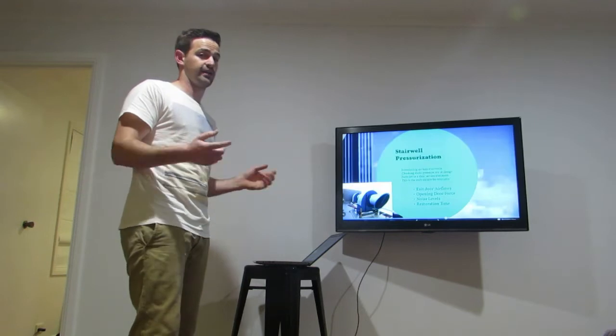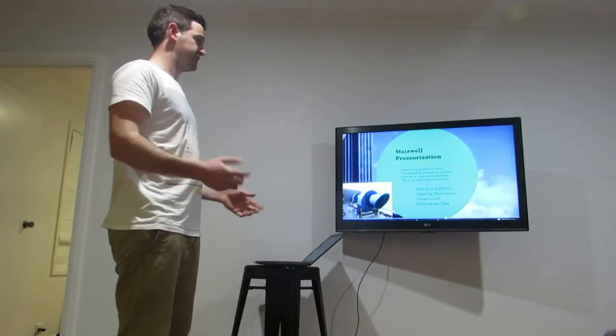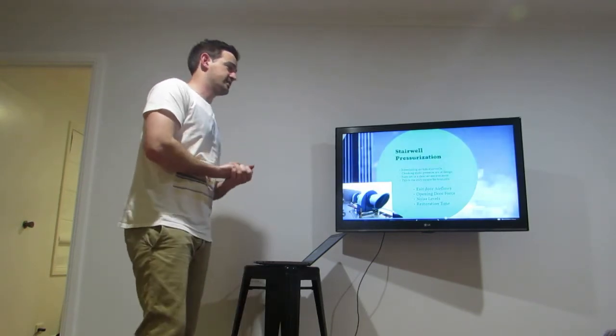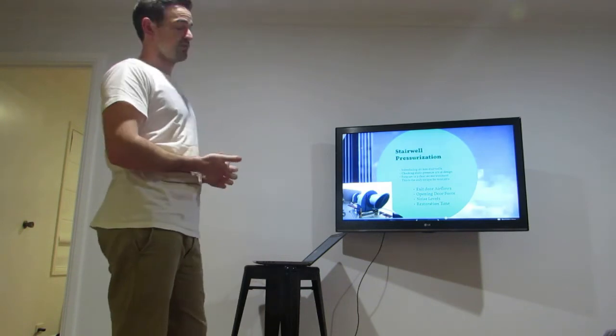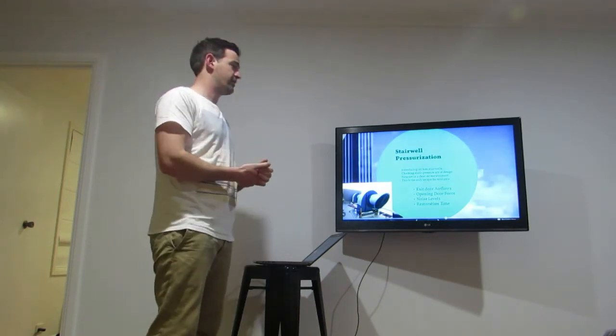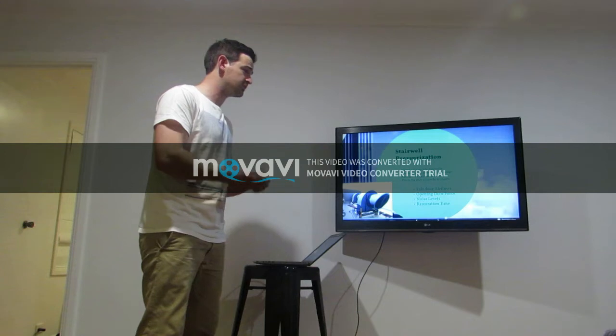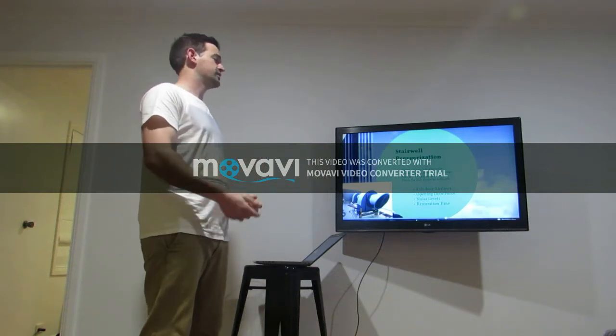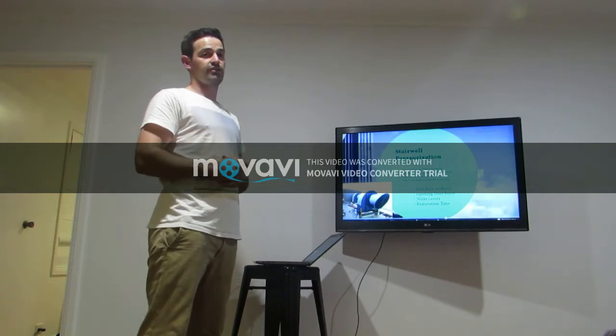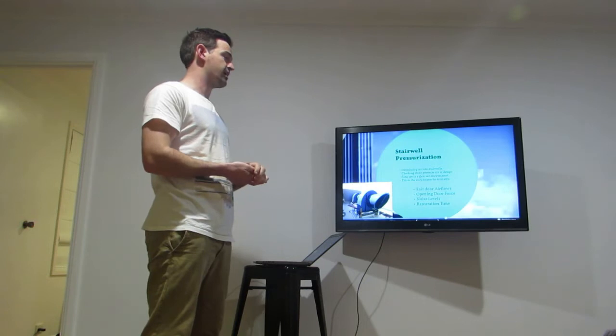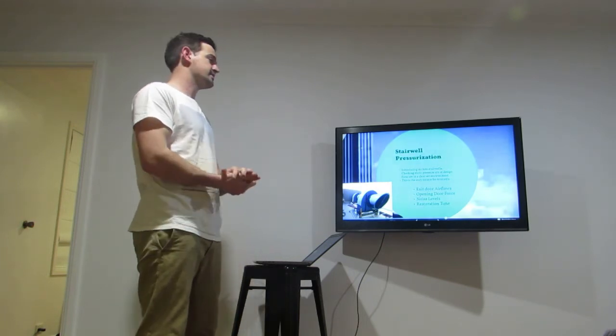This is the only escape for tenants in a multi-storey building. So with stairwell pressurisation, we check exit door airflows. Air across a doorway in a fire exit needs to be at least 1 metre a second. We also check opening door force. A door can't be more than 10 kilograms. This is to allow the elderly, the frail, the young to be able to exit with ease.